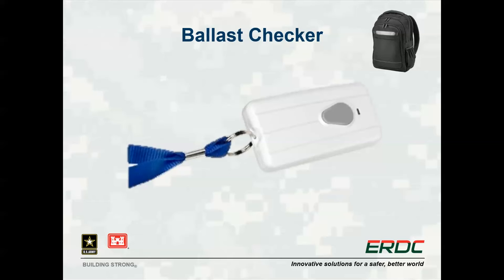The ballast checker can be used to quickly determine if a fluorescent light fixture has a magnetic or electronic ballast. Generally, magnetic ballasts are an older technology and less efficient than electronic ballasts. Determining the ballast type can also help you determine if fixtures are candidates for direct bulb replacement with plug-and-play tube LED bulbs. These bulbs can be used as a direct substitute for T8 or T12 fluorescent bulbs if paired with the appropriate ballast. The 4-foot versions can be purchased for under $10 per bulb and use about half as much electricity as T8s, making this especially noteworthy since tube fluorescent bulbs are among the most common lighting sources in large buildings.